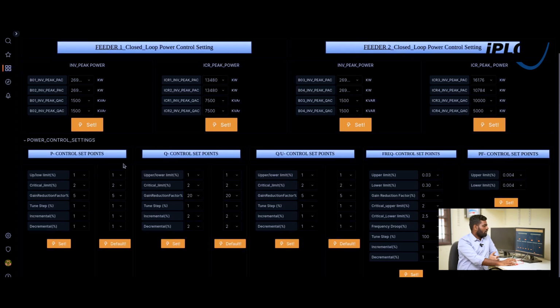And then the power control settings are the set points in our logic. We have mentioned the upper limit, lower limit of active power, gain reduction, critical limit, and similarly for reactive power control also, the upper limit, lower limit, critical limit, gain reduction, and tune step. And similarly for the voltage control set points and frequency control set points, the set point limit, upper limit, lower limit, gain reduction factor, and the critical upper limit and lower limit, we have mentioned here.